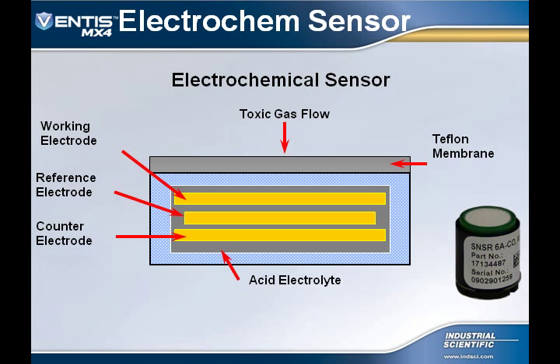Once the gas that the sensor is designed for enters, it is then that the electrolyte creates a chemical reaction within the reservoir, and that chemical reaction will then react with the electrodes and a current is produced. Depending on how high the concentration of gas is within the atmosphere is how much current the sensor will actually produce. So in essence, your Ventis MX4 is a basic digital multimeter measuring the current the sensor is producing. The higher the gas it is exposed to, the higher the current the sensor produces. This in turn gives a higher reading of measurement on a display of the Ventis MX4.